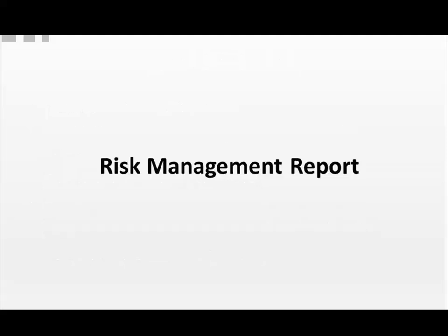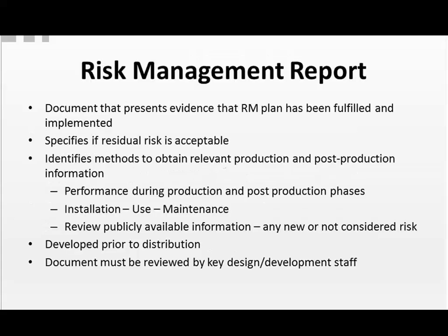Now, we'll end by talking briefly about the risk management report. You really must create a document that presents evidence that the risk management plan has been fulfilled and implemented. It must specify if residual risk is acceptable.